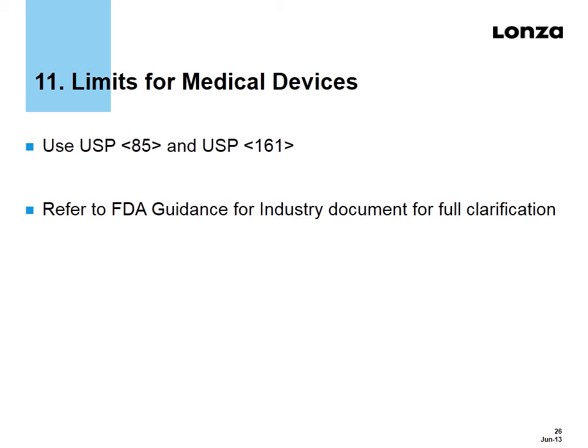subcutaneously. The FDA added information regarding flushing the device for catheters where the internal surface is labeled as non-pyrogenic, disassembly or cutting the device into pieces for devices that are too large to be adequately rinsed, and also immersion for implantable devices.